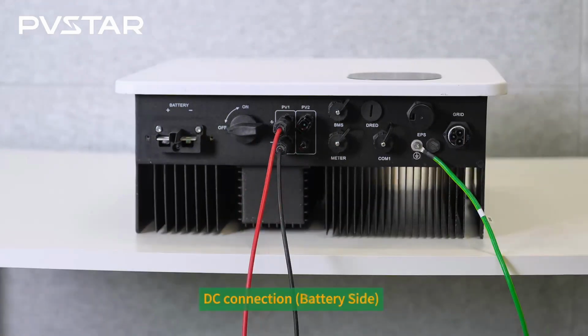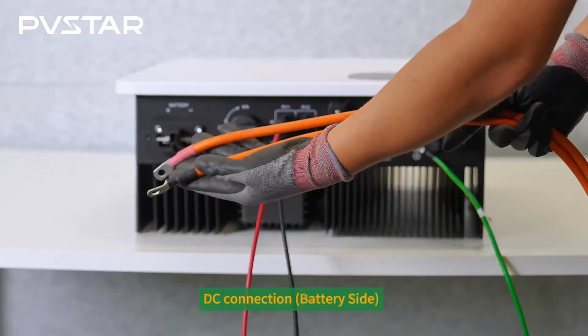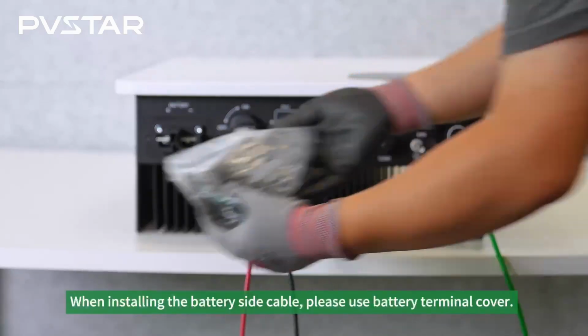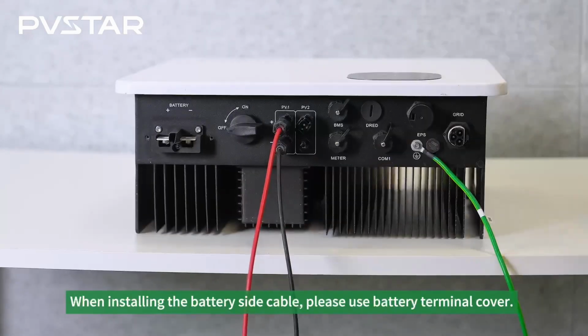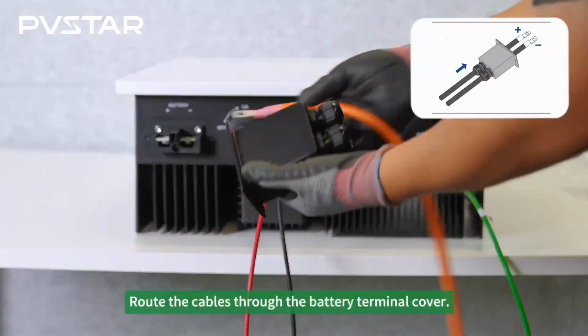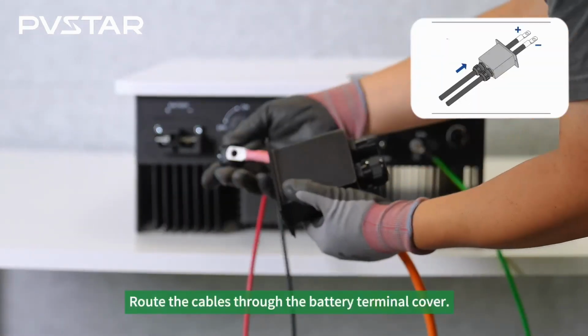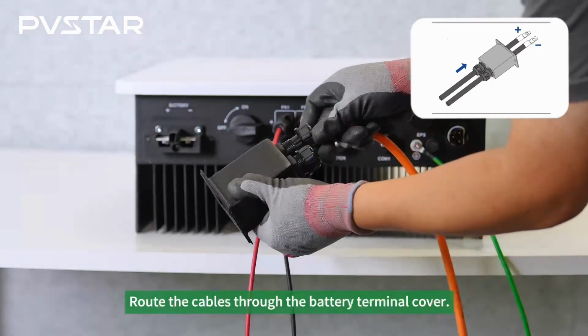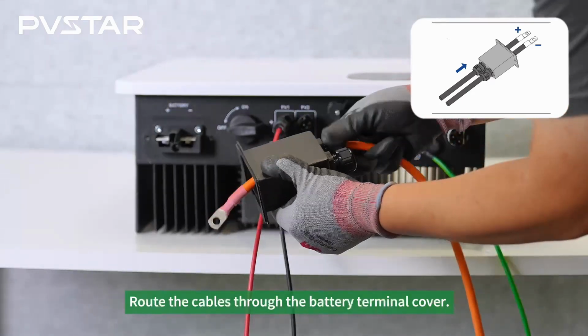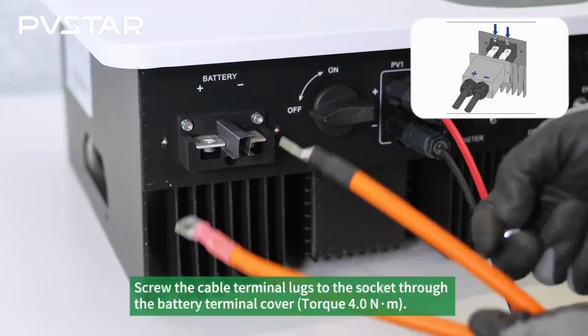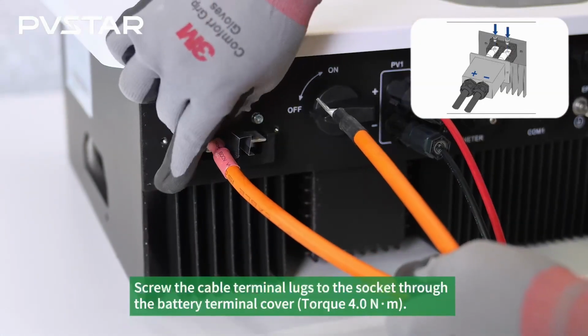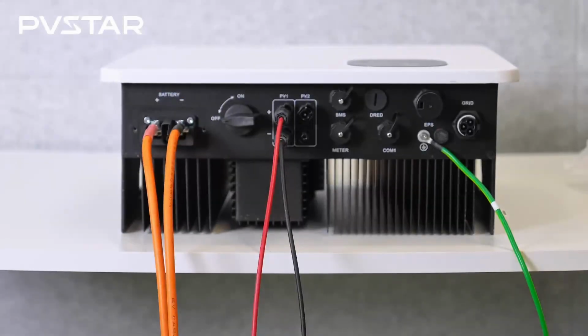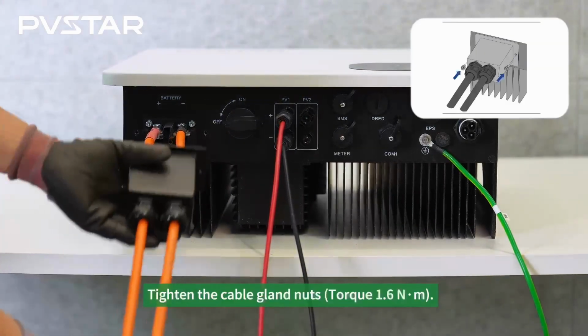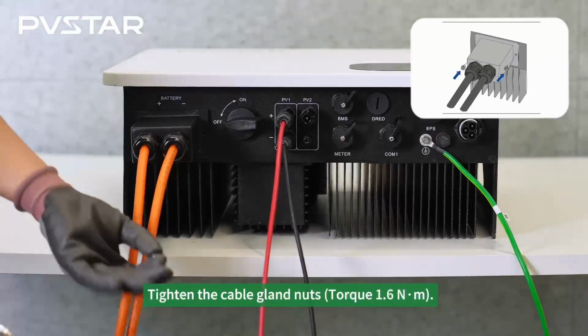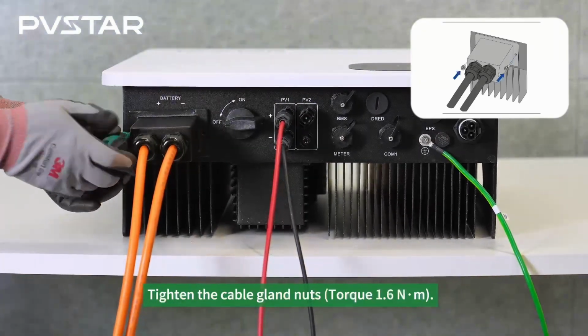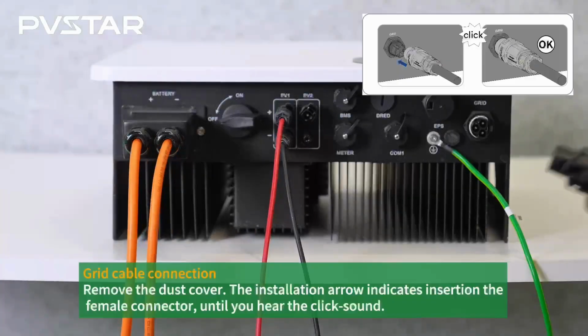After that, we will do the DC connection on the battery side. When installing the battery side cable, please use the battery terminal cover. Route the cables through the battery terminal cover. Screw the cable terminal lugs to the socket through the battery terminal cover. Tighten the cable gland nuts. In the next step, we will do the grid cable connection.